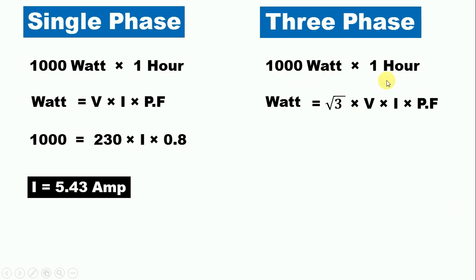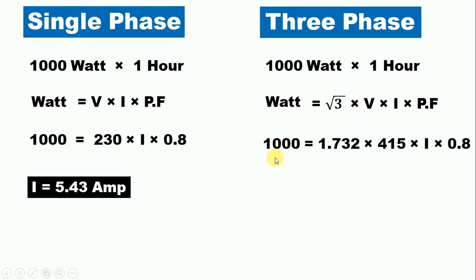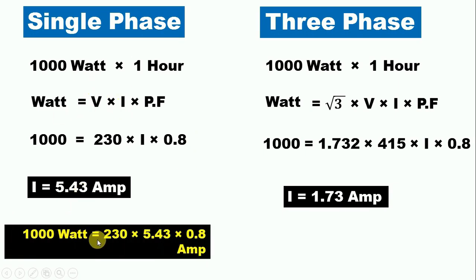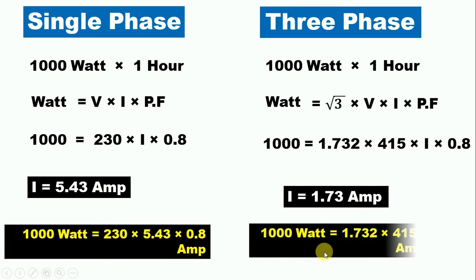Now for three phase, the formula is P = √3 × V × I × power factor. In place of power we put 1000 watt, the value of √3 is 1.732, voltage is 415 volt, power factor is 0.8, and we solve for current. The answer comes out as 1.73 ampere. So if the load is 1000 watt connected to three phase power supply, it draws 1.73 ampere. If we put this value of current back into the formula, the value of power is the same — power of single phase and power of three phase are equal.